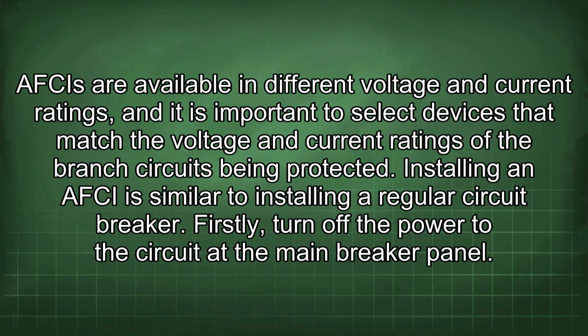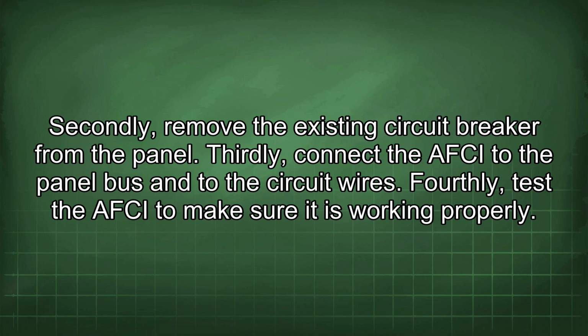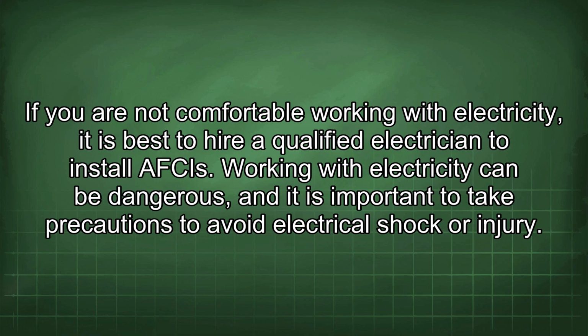Installing an AFCI is similar to installing a regular circuit breaker. Firstly, turn off the power to the circuit at the main breaker panel. Secondly, remove the existing circuit breaker from the panel. Thirdly, connect the AFCI to the panel bus and to the circuit wires. Fourthly, test the AFCI to make sure it is working properly. If you are not comfortable working with electricity, it is best to hire a qualified electrician to install AFCIs. Working with electricity can be dangerous, and it is important to take precautions to avoid electrical shock or injury.